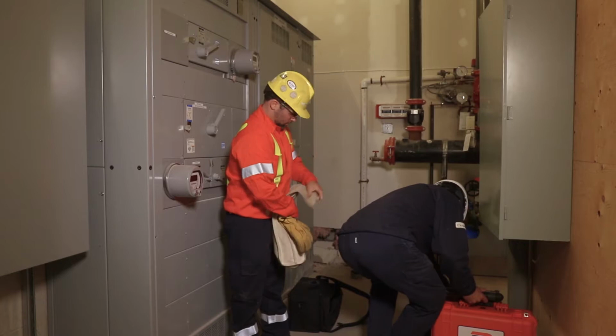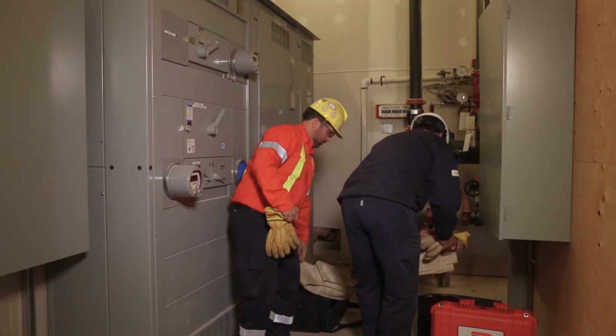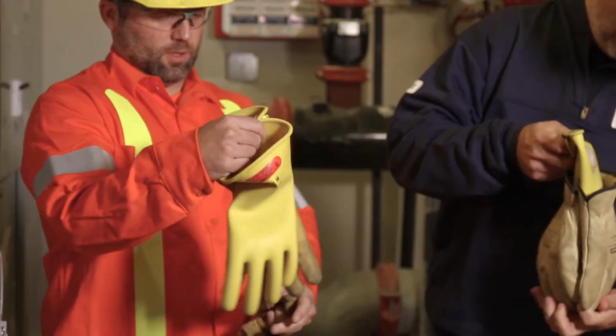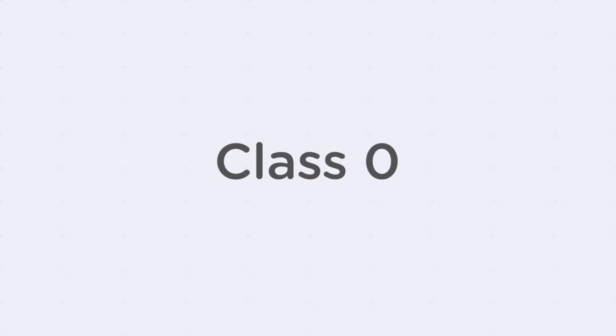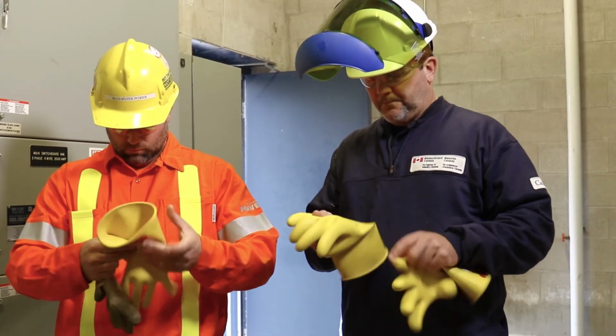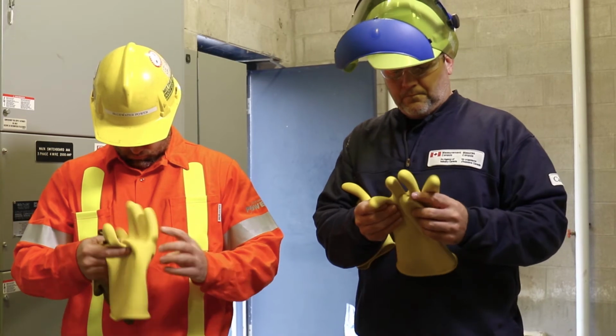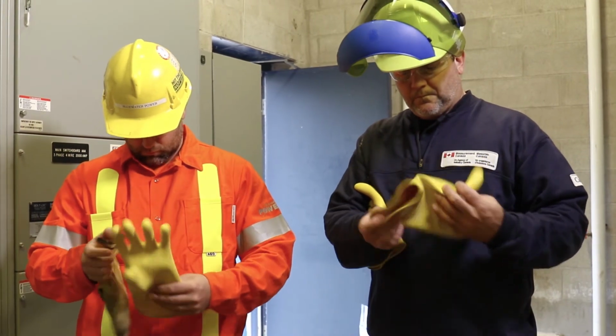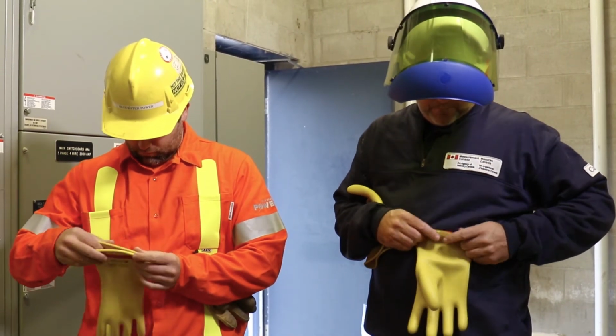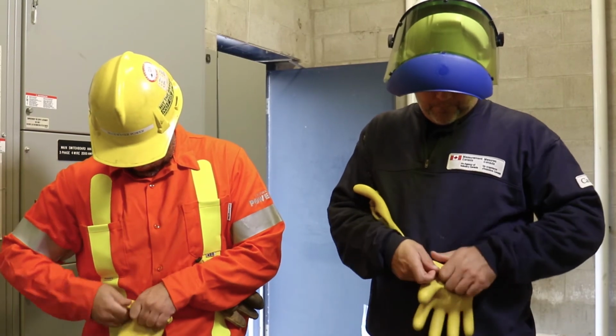For any electrical installation inspection, voltage-rated rubber gloves are required to meet Class 0 and must be used in conjunction with leather gloves to protect the rubber. Ensure that rubber gloves have not been excessively worn and are free of pinholes, cuts and abrasions, and are free of debris that could damage the gloves. Before wearing rubber gloves, inspect them visually. Ensure they are within the expiry and inspection dates, and perform a field leak test before daily use.